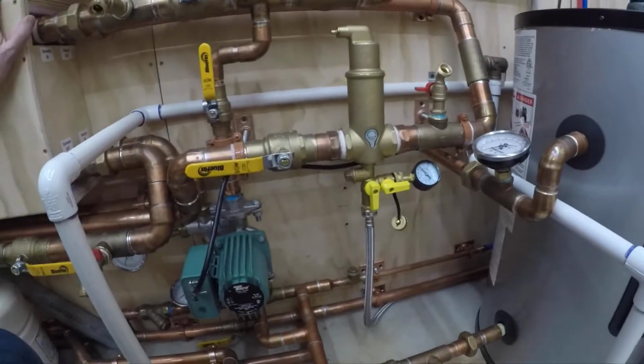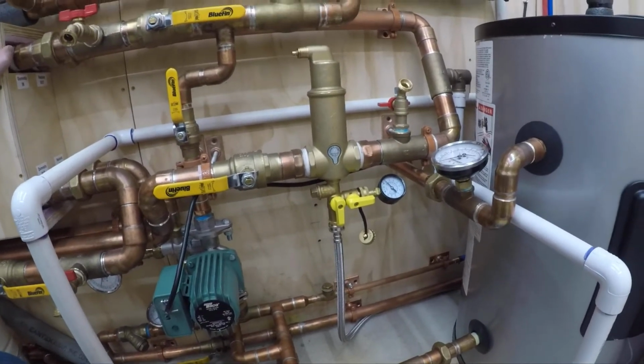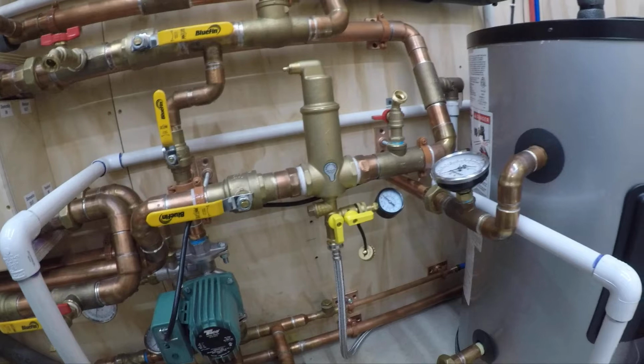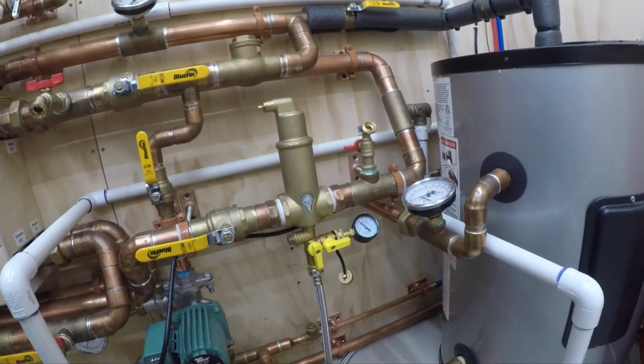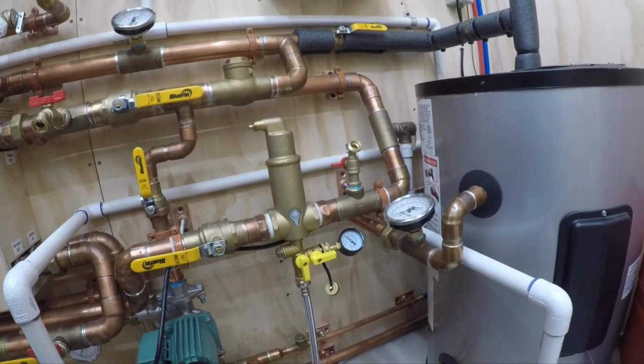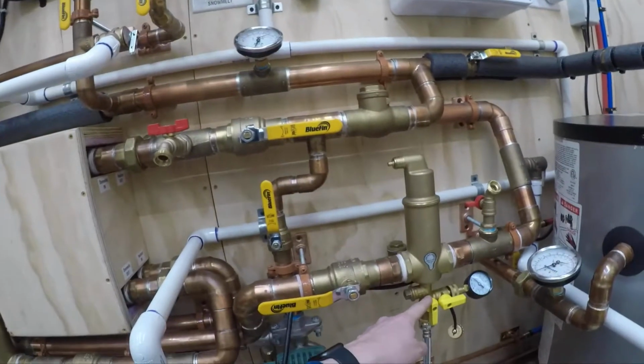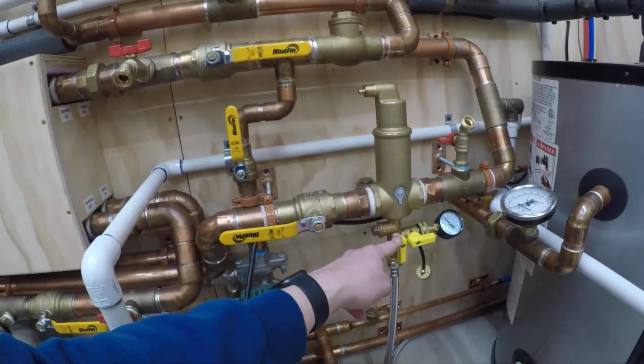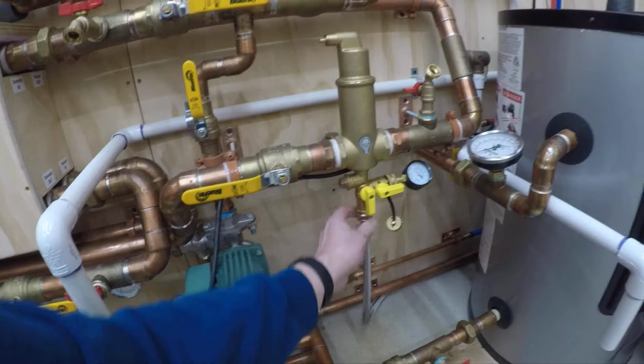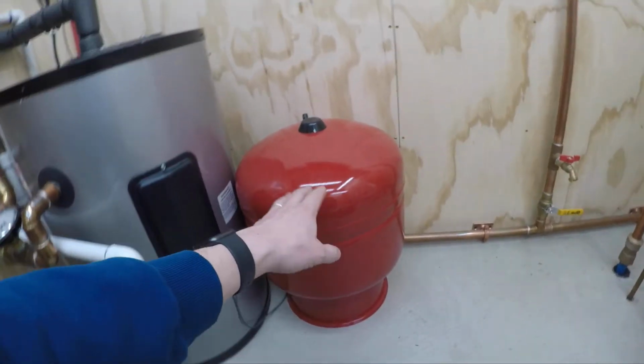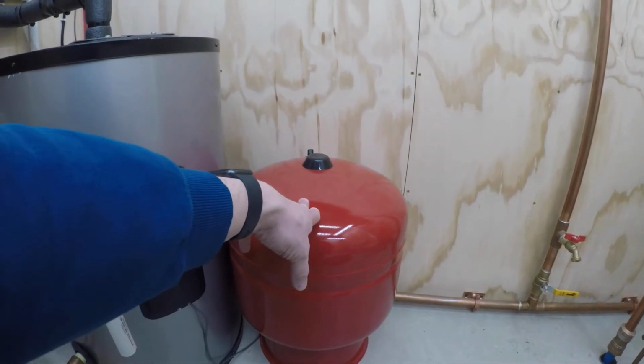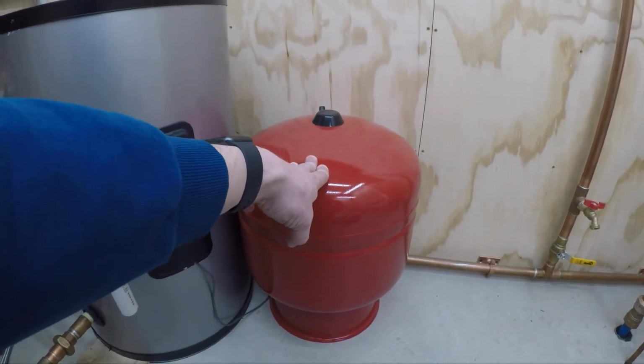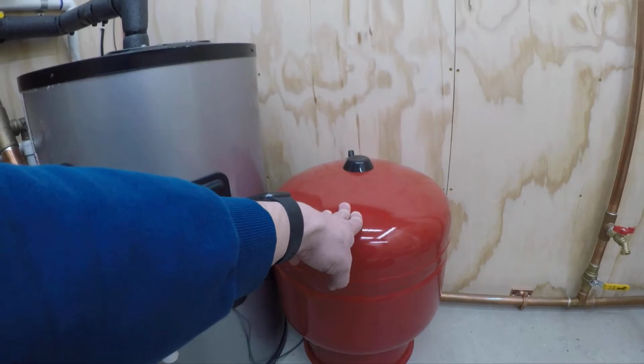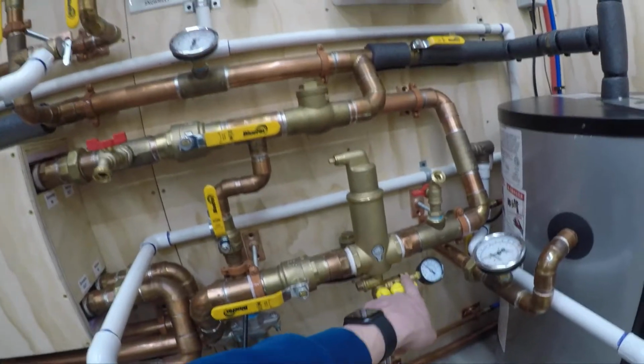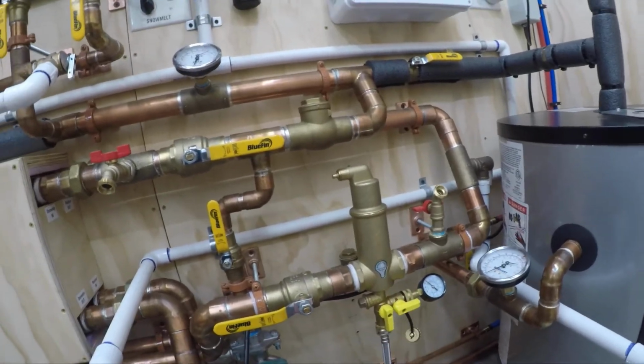Originally I had the gray one, which is meant for just your normal boiler water that you see with boilers, you know, baseboard hot water or whatever. So I bought a little propane valve here and just hooked up my tank. This runs through the stainless steel braided line around the back into the bottom. This is pressurized to 14 pounds, which is what my heating side of the system is at. And on here I just put a gauge on it to help when I was filling it.